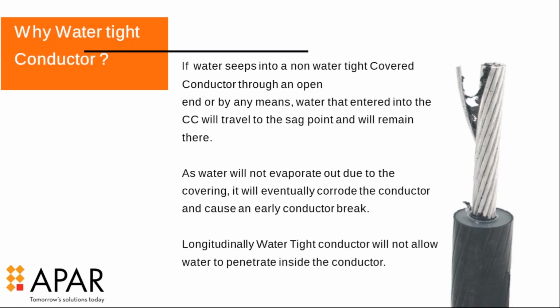At the operational temperature, this water converts to steam and cracks the XLPE, trying to escape. This harms the covered conductor and reduces its life. So a longitudinally watertight conductor does not allow water to penetrate inside. This is a very important feature to consider while choosing covered conductors.